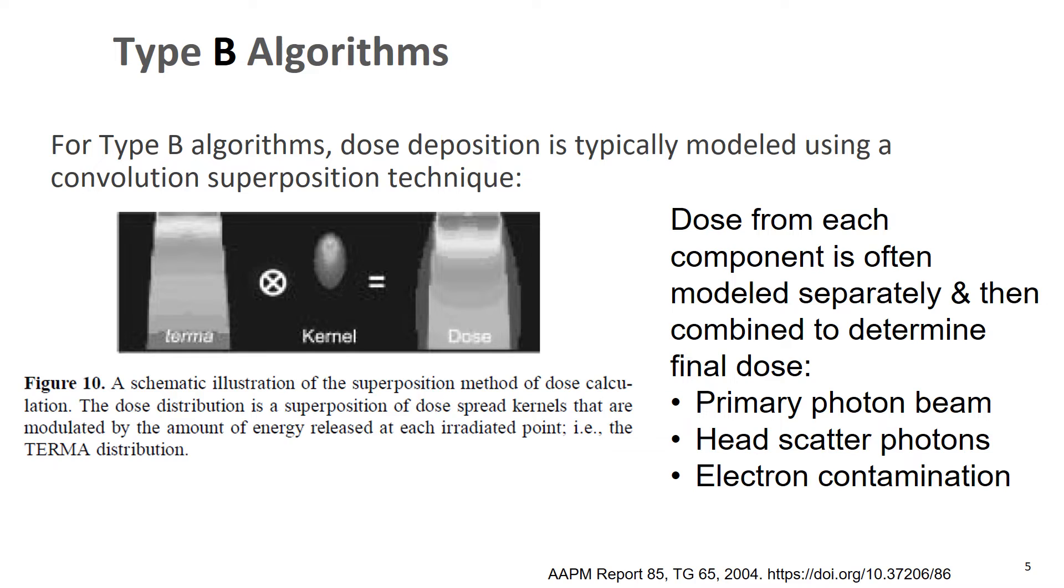And just a little more detail about how these algorithms work. So type B algorithms, the dose deposition is typically modeled using a convolution superposition technique. So you can see in this figure here on the left, we have the terma, and then we have a dose convolution kernel. And so you convolve that terma with that dose kernel and you end up with dose.